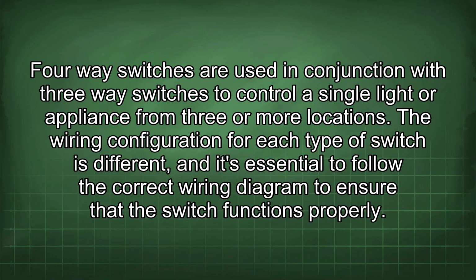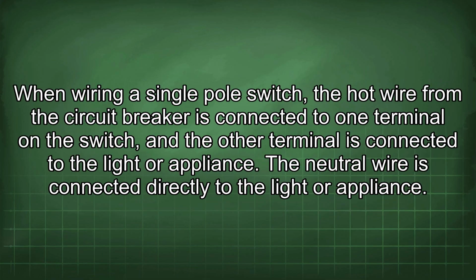Three-way switches, on the other hand, are used to control a single light or appliance from 2 different locations. Four-way switches are used in conjunction with three-way switches to control a single light or appliance from 3 or more locations. The wiring configuration for each type of switch is different, and it's essential to follow the correct wiring diagram to ensure that the switch functions properly. When wiring a single-pole switch, a hot wire from the circuit breaker is connected to one terminal on the switch, and the other terminal is connected to the light or appliance.